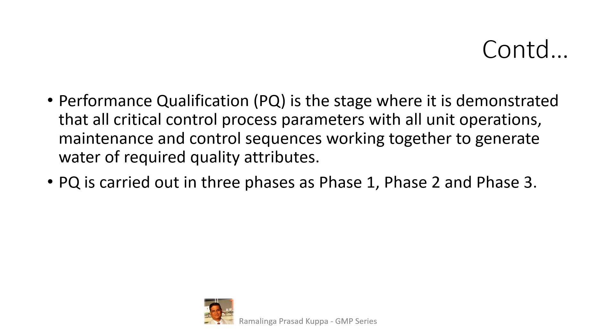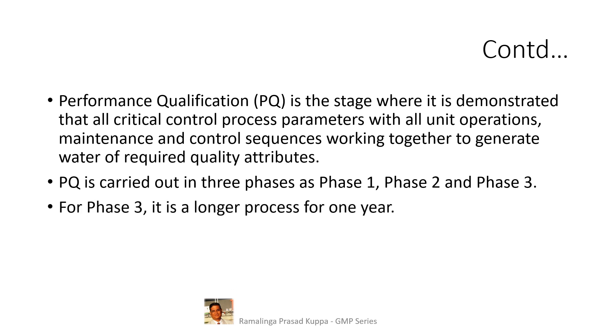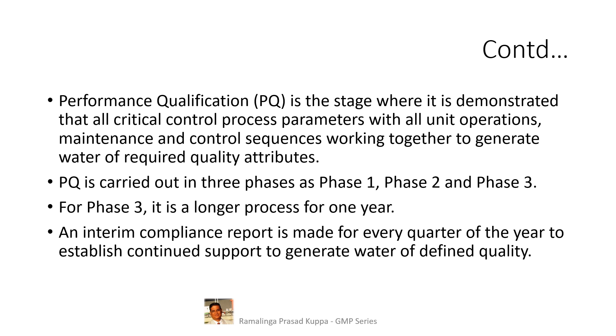Phase 3 is carried out after successful completion of phase 1 and phase 2. It is a longer process of 1 year, carried out to cover data from all seasons of the year — a 12-month period. Reduced sampling and testing, as in phase 2, may be designed for both chemical and microbial attributes. An interim compliance report is made for every quarter of the year to establish continued support in generating water of defined quality. This is important as it captures how quality attributes vary seasonally.